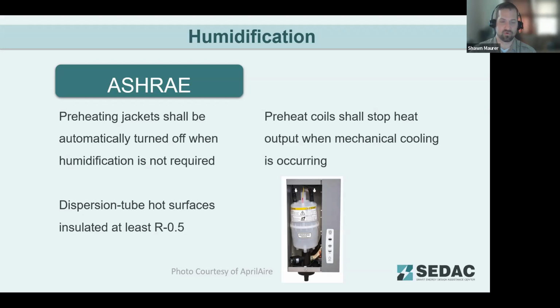And dispersion tube surfaces for those humidifiers should be insulated to at least an R-0.5. These features make sense as you don't want to add heat to the system when it's not needed, and you want the humidifying heat to stay in the vapor so that when it hits the airstream, it readily evaporates. You don't want it getting cooler in the piping before it gets sprayed into the airstream. So understanding that when humidification is not needed, that source of heat should be turned off so you're not fighting that system for cooling capacity. Similarly, when operating mechanical cooling, preheat coils or freeze protection coils add a false load to the cooling system. We've seen that done for humidity control. They're trying to prevent that here with this requirement.